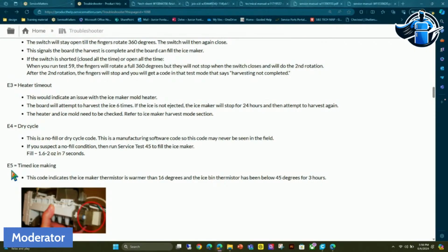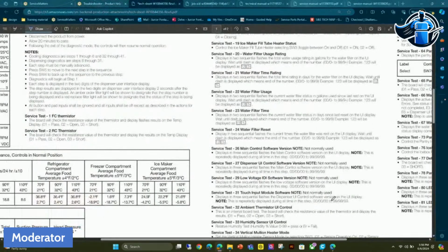So when you put a new ice maker in, you have to clear the fault code. The only way to clear a fault code on this unit is to unplug it from the wall and plug it back in. That cycles the controls and clears the fault code, which you should be doing anyway, since you don't want to be replacing ice makers while power is still running through the unit. Make sure you clear all fault codes before attempting to run this ice maker. It will run fine in diagnostics, but once you get out of the diagnostic cycle, the customer will never get ice out of it because it won't operate in normal operation.